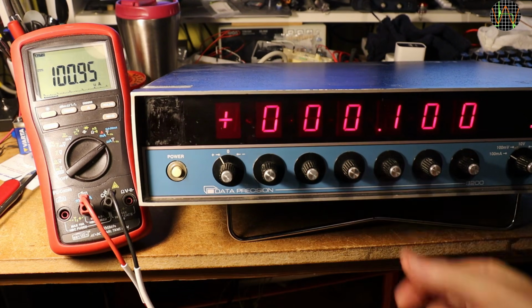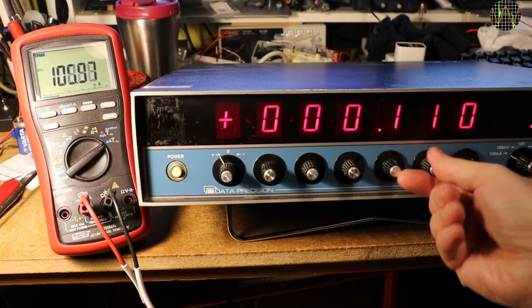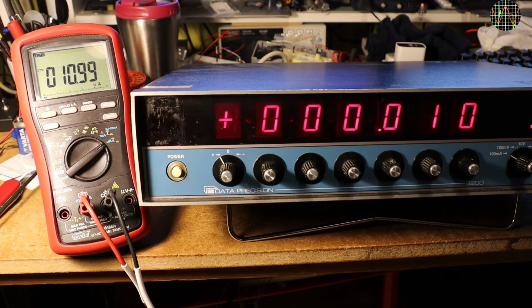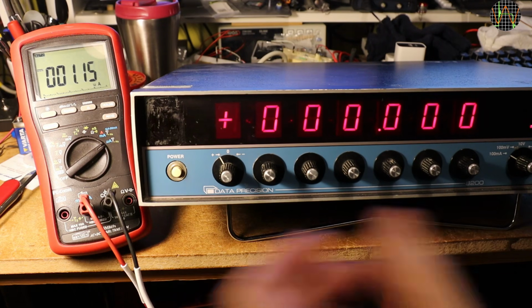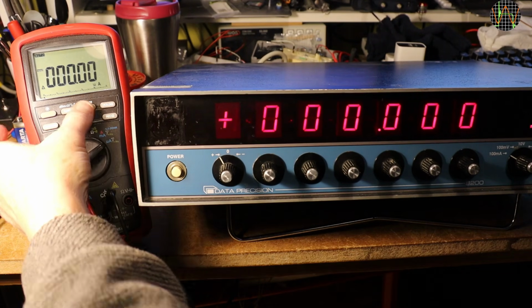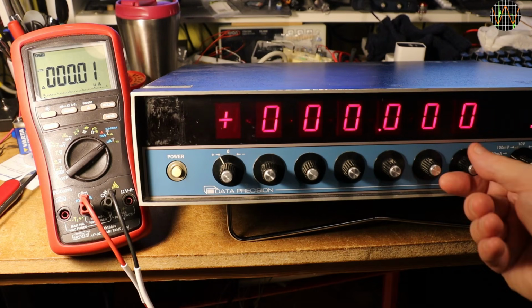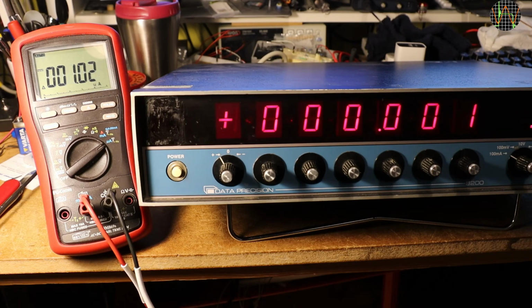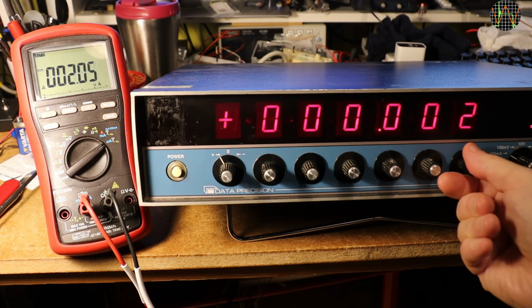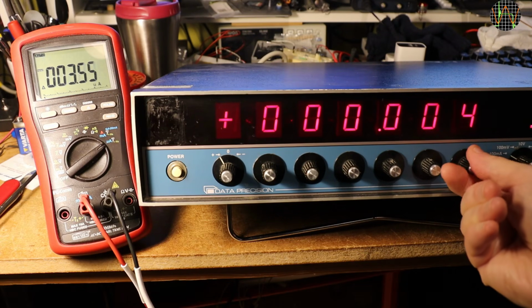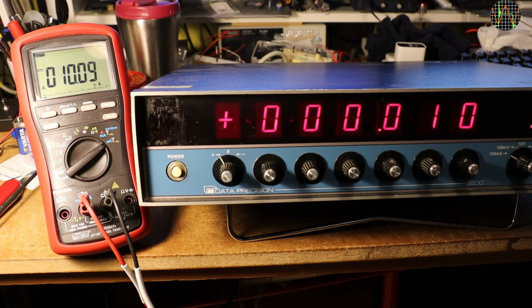Let's try a low current, for example 0.1 milliamp, and that works fine. 10 microamps is similar, and we are probably again in the range of currents caused by thermal EMF. So let's select 0 milliamp output and rel the meter and see if that helps. Selecting 1 microamp, and yes, that looks very close. 2, 3, 4 and so on, all the way to 10 microamps, no problem.